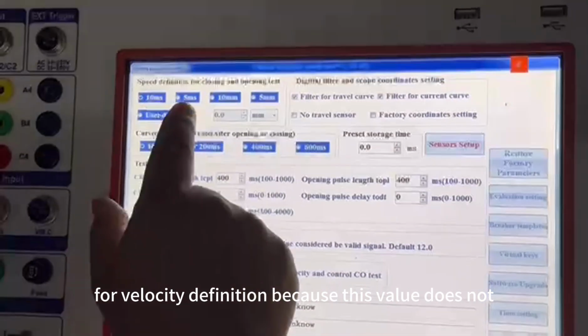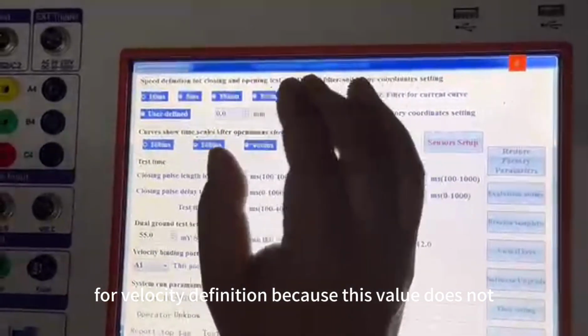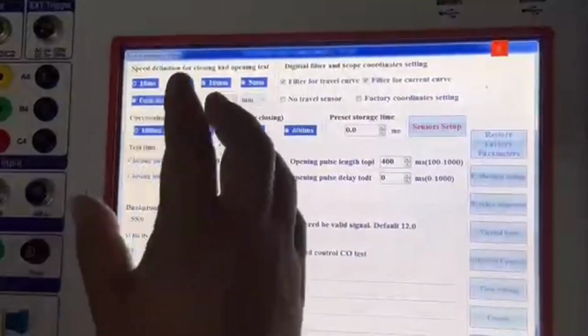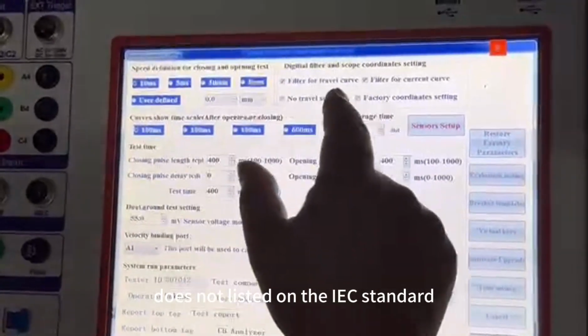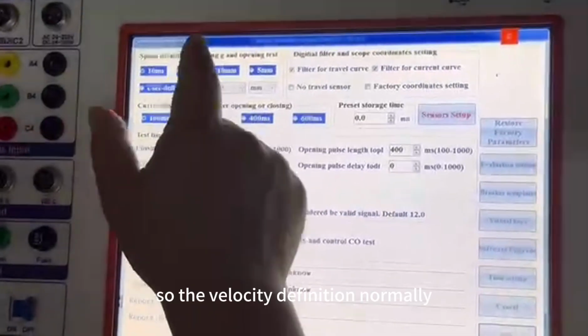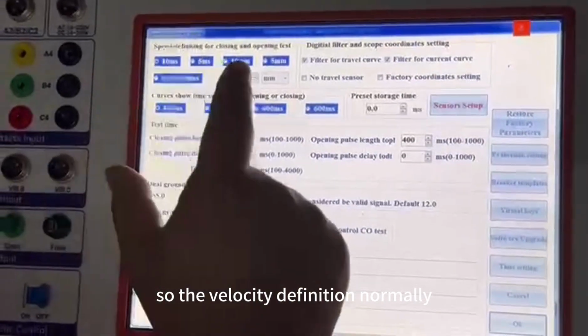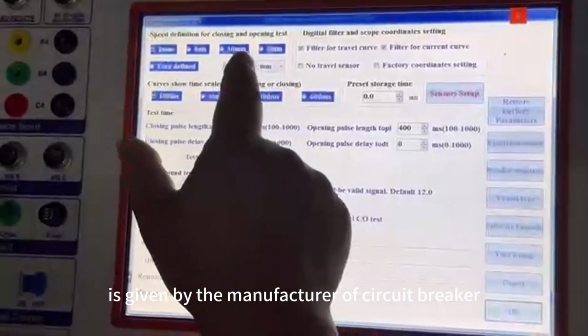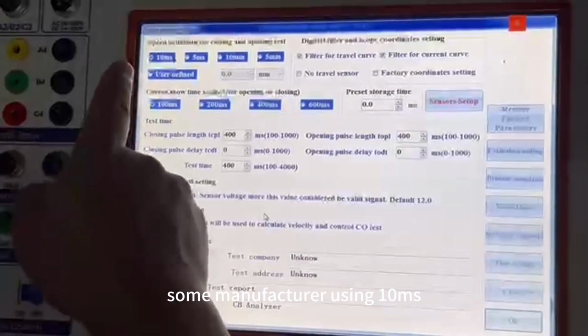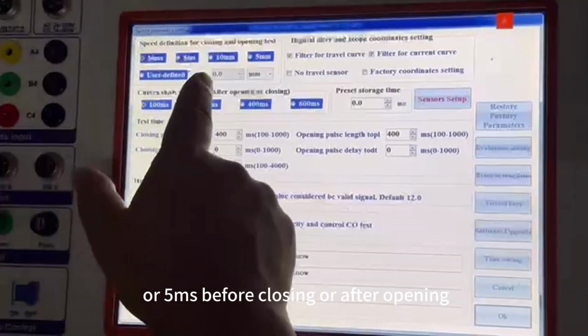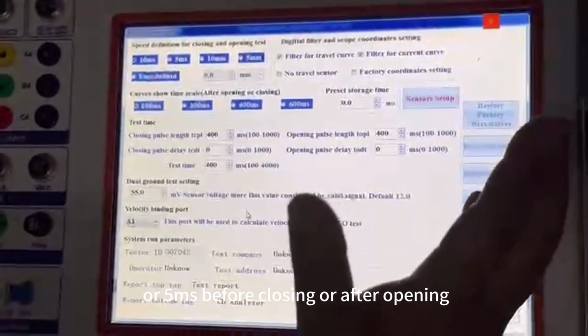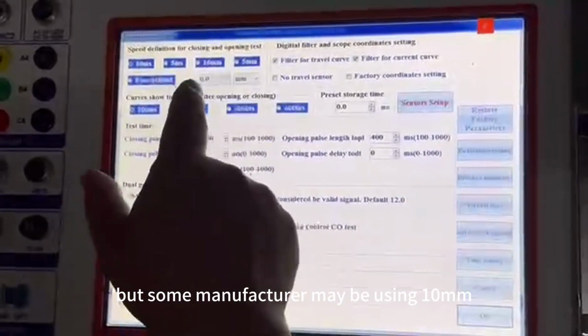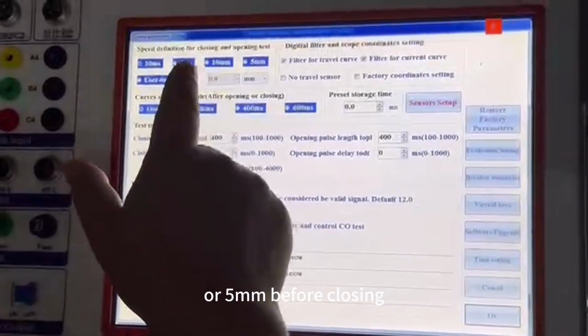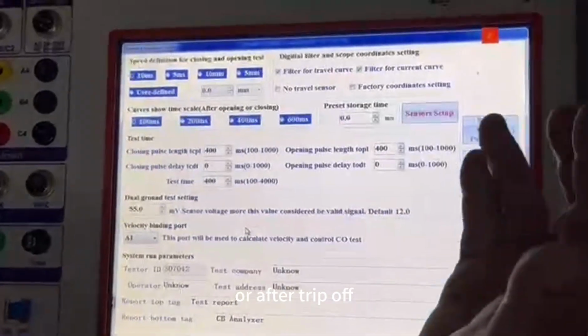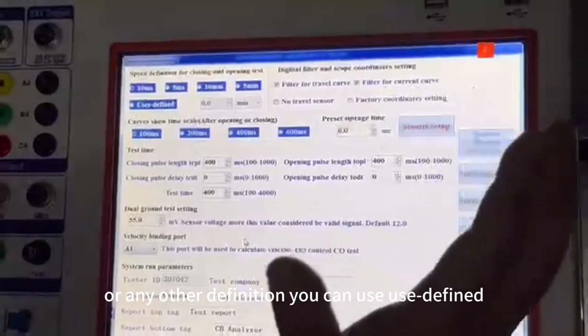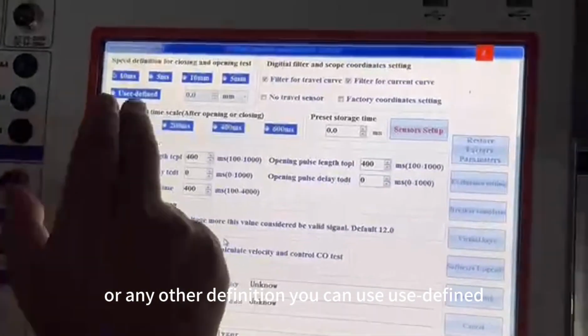For velocity definition, because this value is not listed in the IEC standard, the velocity definition normally is given by the manufacturer of the circuit breaker. Some manufacturers use 10 milliseconds or 5 milliseconds before closing or after opening. But some manufacturers may use 10 millimeters or 5 millimeters before closing or after trip off. Or any other definition you can use user-defined.